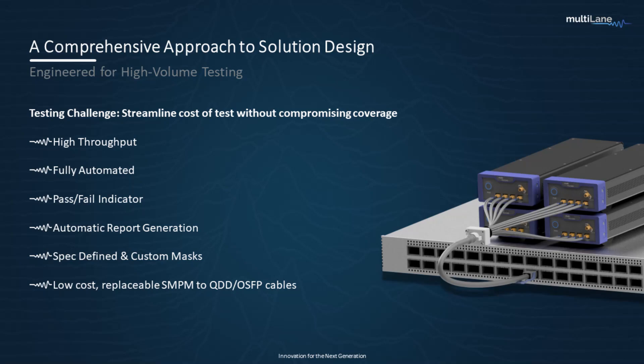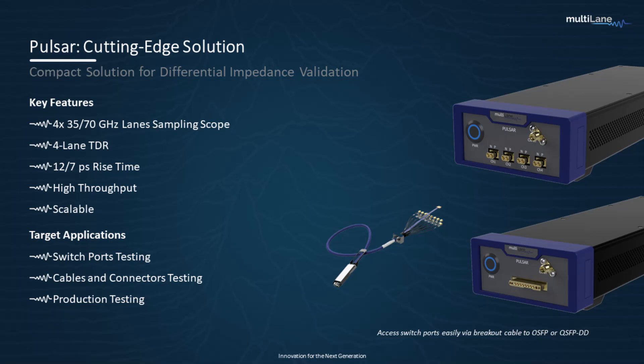Let's have a quick look at the instrument proper. Pulsar is a four-lane scope and TDR available in 35 and 70 gigahertz bandwidth. 35 or 70 gigahertz bandwidth brings us down to 12 or 7 picosecond rise time respectively. And to keep things moving fast, we have scaled down testing time to a few seconds, which makes Pulsar a high-throughput scalable instrument.